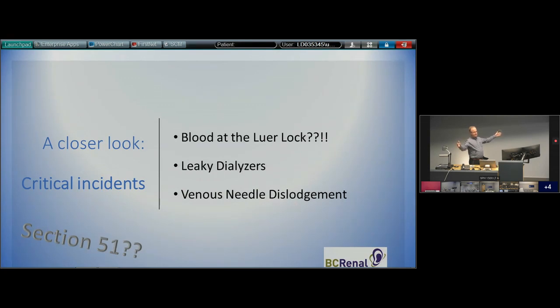And all of a sudden, within days, we were getting reports from around the province that a certain manufacturer's stable of dialyzers were cracking. So we were able to have an immediate get-together, get all the hemo leads together, find out what's going on, and then broadcast around to the programs to say this is going on, watch out for these dialyzers - maybe we should take this particular brand off the shelf until we know what's going on. So that was an important safety thing.